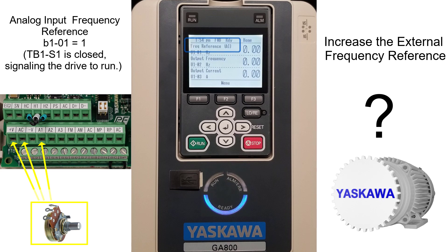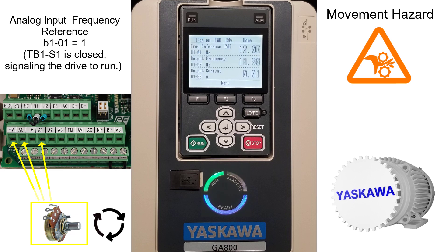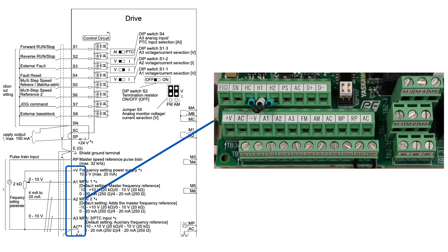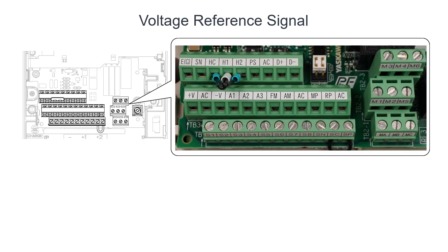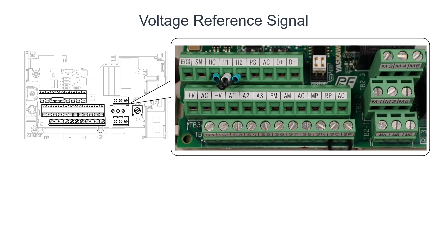If you are using an external frequency reference and the LO/RE LED is off, indicating remote run control, increase the frequency or signal and see if the drive begins to spin the motor. If this does not work, you need to check the reference signal wiring. Use the connection and input-output diagrams to verify the signal wiring. If the reference signal is voltage and uses two wires, verify which wires are signal and common — make sure the signal wire connects to A1 and the common to AC. Once you have verified the wiring, try running the motor again.